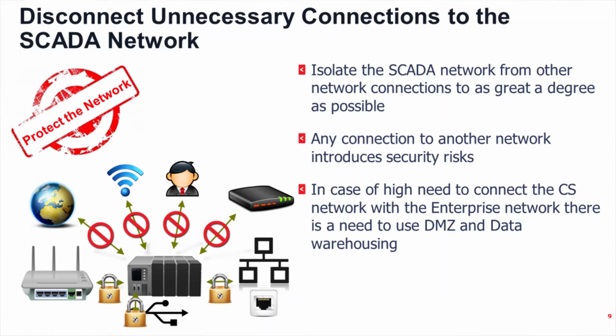Commandment 2: Disconnect unnecessary connections to the SCADA network. Isolate the SCADA network from other network connections to as great a degree as possible. Any connection to another network introduces security risks. In case of a high need to connect the control system network with the enterprise network, use a DMZ and data warehousing.